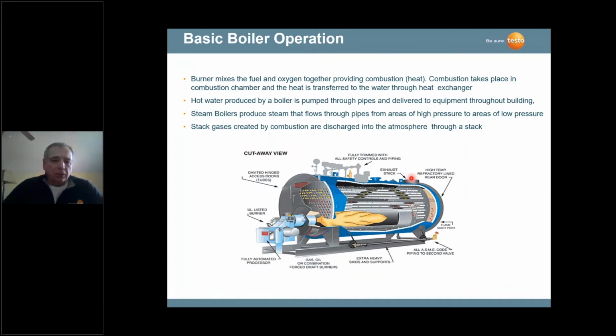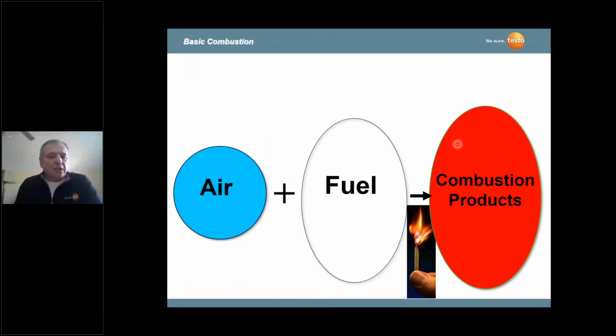And here are the gases. This is what we're actually measuring. When we measure the stack gases for oxygen, carbon monoxide, and stack temperature, we're also looking at how this burner is operating. The byproducts of combustion help lead us to issues with burner performance. That's the big thing with combustion analyzers: they're used for energy efficiency, for combustion safety, and also for compliance.